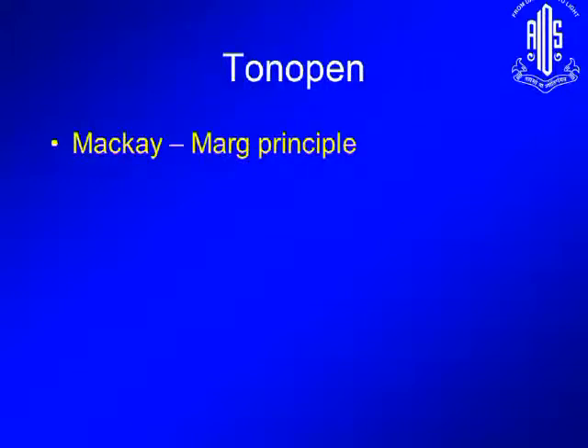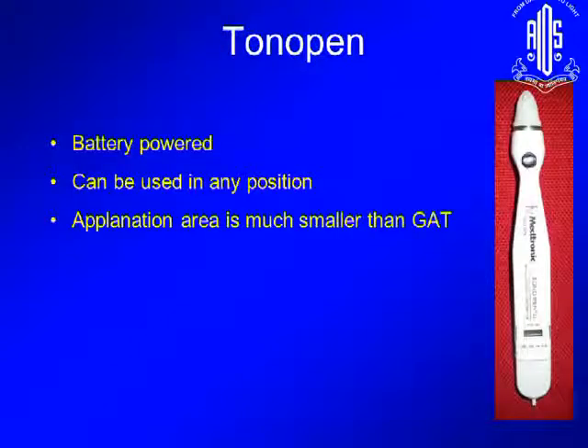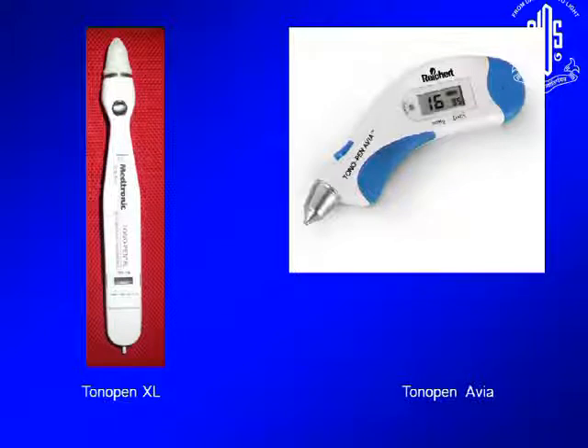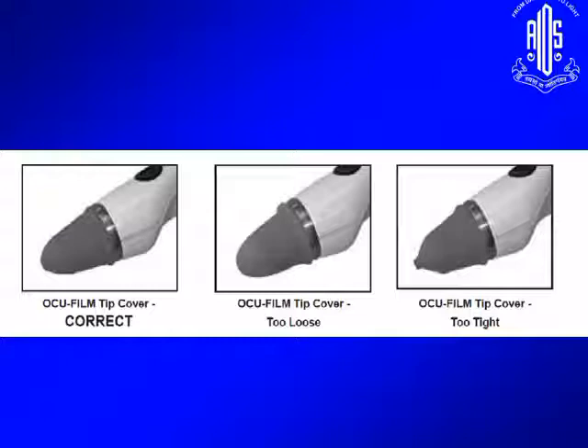The Tonopen is based on the Mackay-Marg principle. I'm not really going to go into details about that. It's battery operated, can be used in any position, and the applanation tip is much smaller than the Goldmann applanation tip, which means in a scarred cornea too, you can get reasonable readings. You have two models out there. One is the Tono-Pen XL, which is the older model, and the Tono-Pen Avia, which is the newer model. The basic principle is the same, and before you do that, you need to use this tip, which can be sterile or unsterile, and you may need to make sure that you put that on correctly so that it's not too loose or too tight and affects your readings that way.